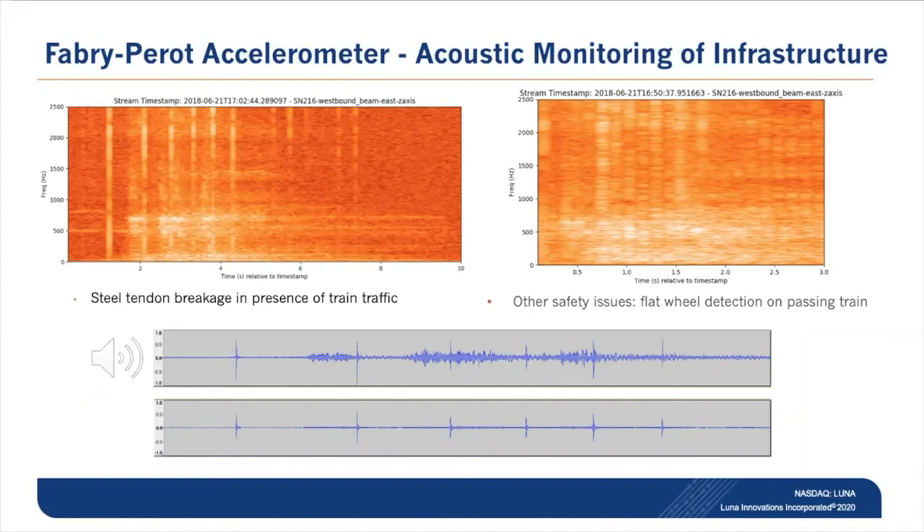The bottom plot shows further filtering that allows easy threshold detection to identify where wire break events occurred. As an added bonus while monitoring, a local engineer noted we had captured a wheel hammer event — a flat spot on a train wheel — visible as broad-spectrum periodic noise that correlates directly with the wheel diameter and the rate at which the train was traveling. This is additional benefit that can be derived from an instrumented structure in terms of monitoring the health of assets that travel over it.